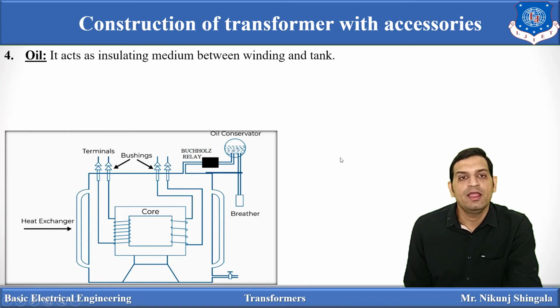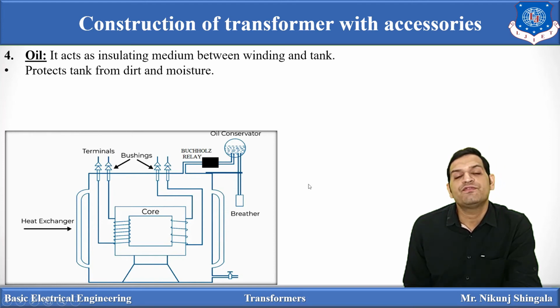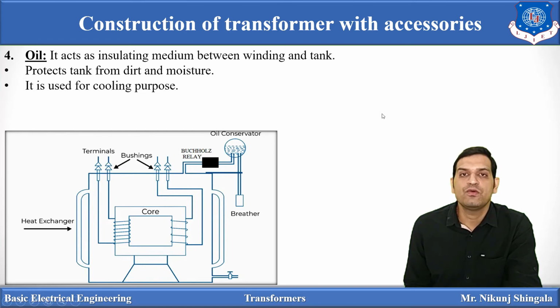The next one is oil. Basically, it acts as an insulating medium between winding and tank. If oil is not provided, there may be a possibility of short circuit. Now, what is the purpose of the oil? It protects the internal part of the tank from dirt and moisture. And it is basically used for cooling. When supply is given to the coil, it may get heated. So the purpose of the oil is to provide cooling in the tank.